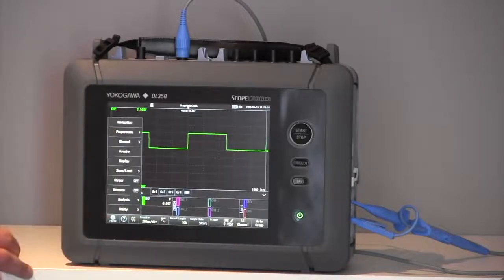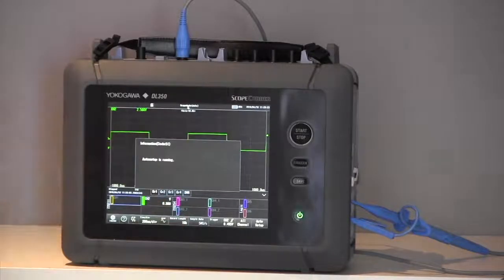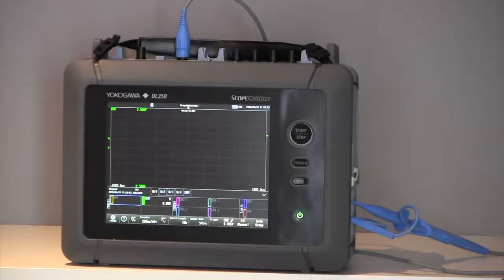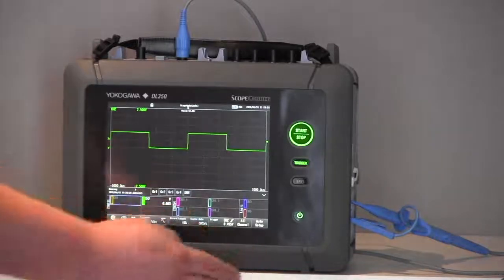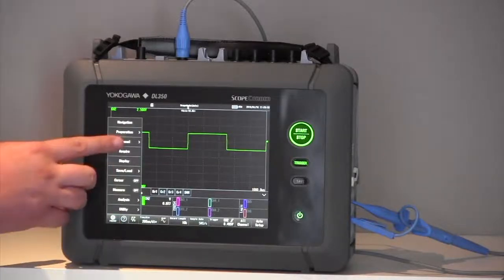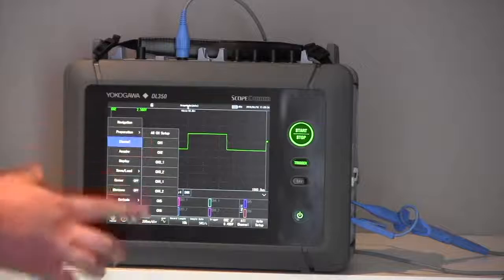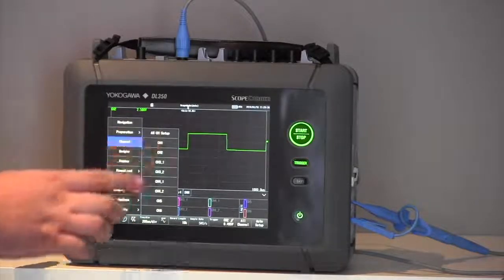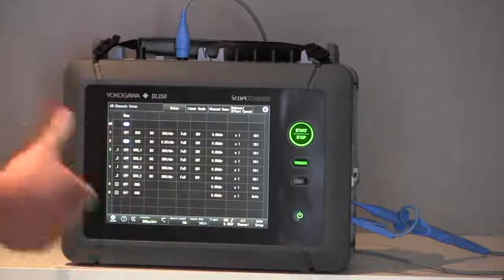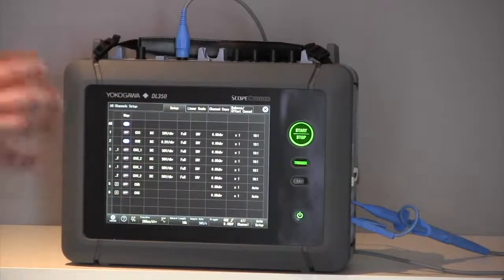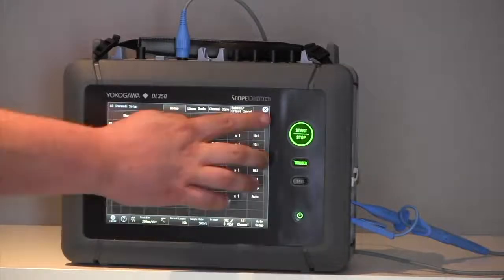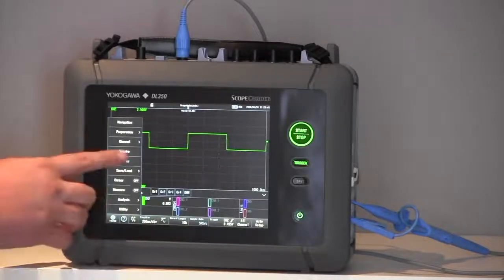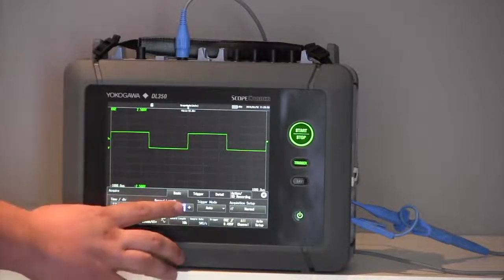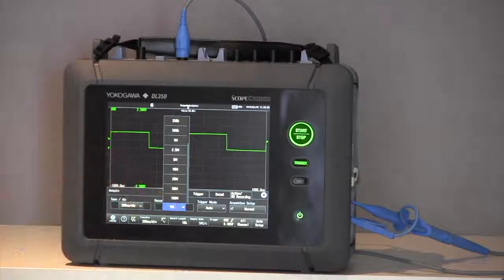Scope mode allows me to do what is commonly found on oscilloscopes, which is do an auto setup. Auto setup detects the channels that are active and turns off the channels that are not active. With this menu as well, I can move into the channel menu and change individual channel settings, or at the top we have all channel setup, which allows me to look at a full matrix of all of the channels so that I can change them all on one table. Other options within the menu include Acquire. Acquire allows me to change the record length, and from here I can go all the way up to 100 million points of data per module slot.